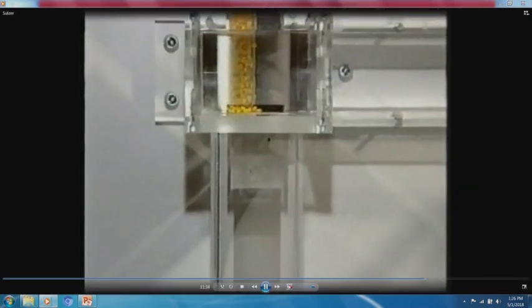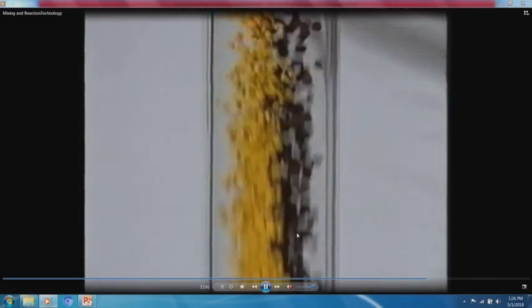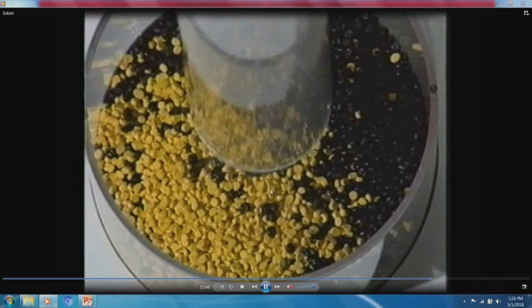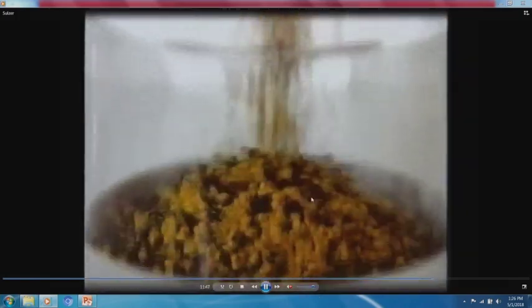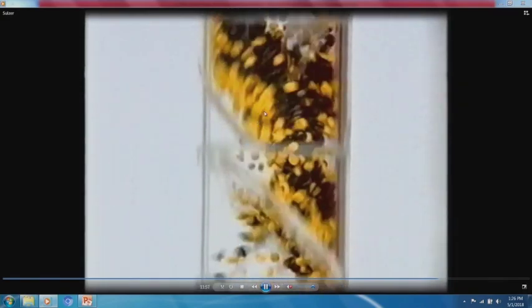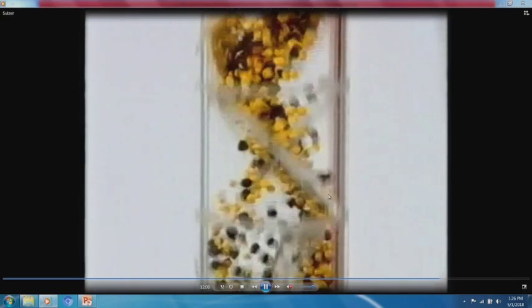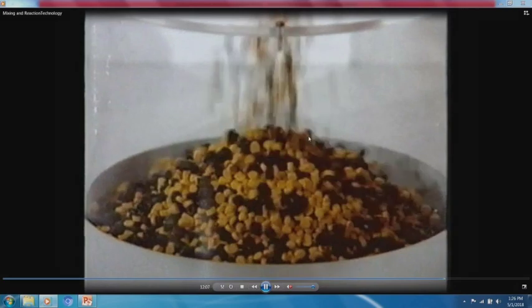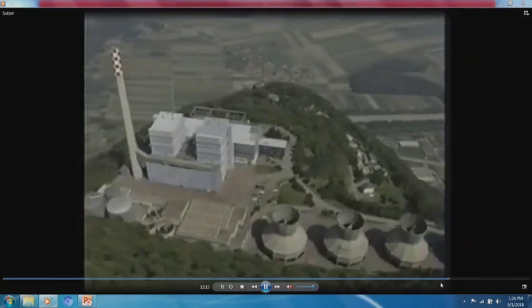Now, there is a claim that static mixers may be used for solids. Here they're showing you yellow and black falling straight in a tube. They're unmixed when they went in. They're fairly unmixed when they leave. You throw it through a static mixer back and forth, and they mix quite well. The problem with this is that if this was operating under a continual system and there was significant abrasive material, your static mixer may actually disappear on you, right? The static mixer would be essentially abraded away.